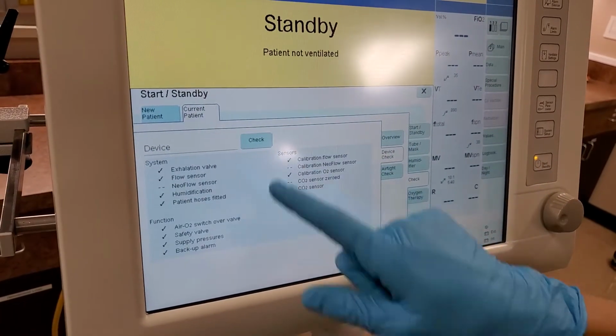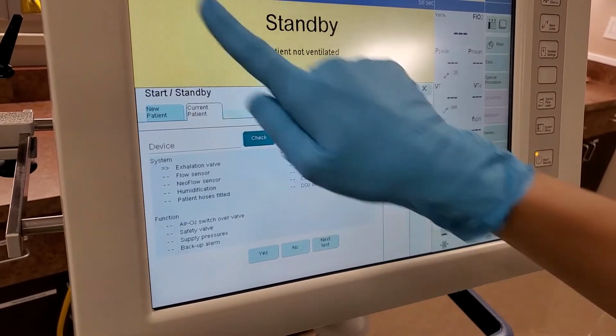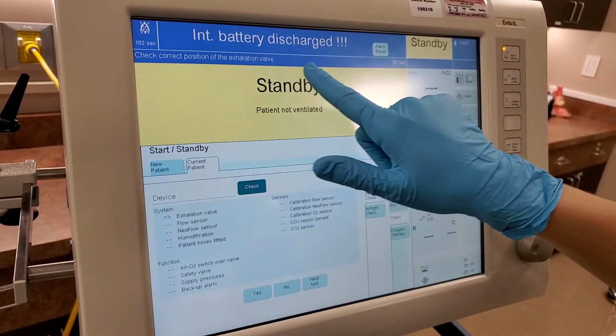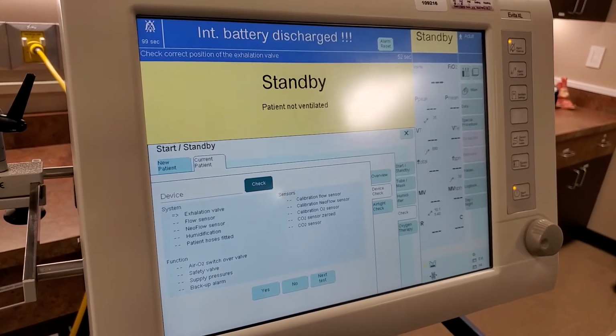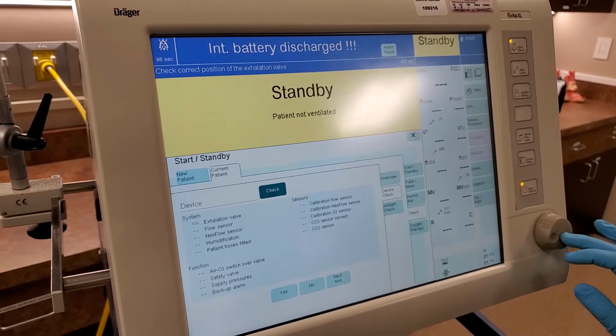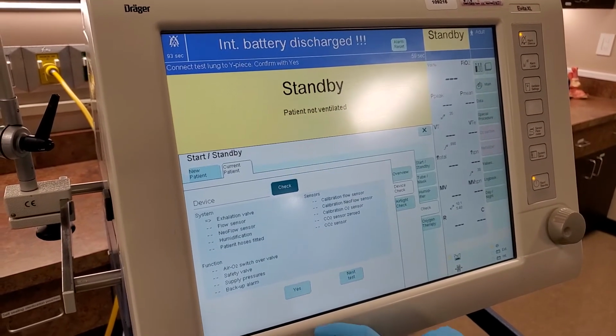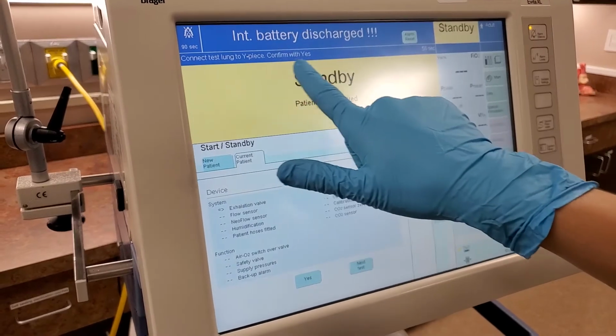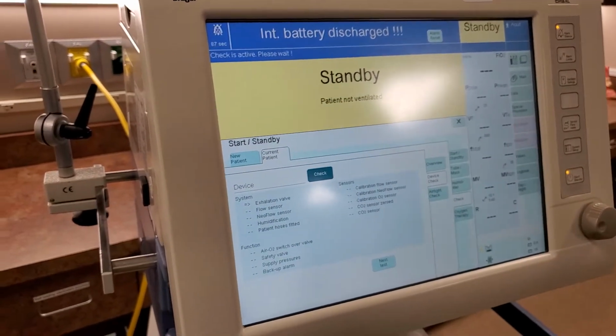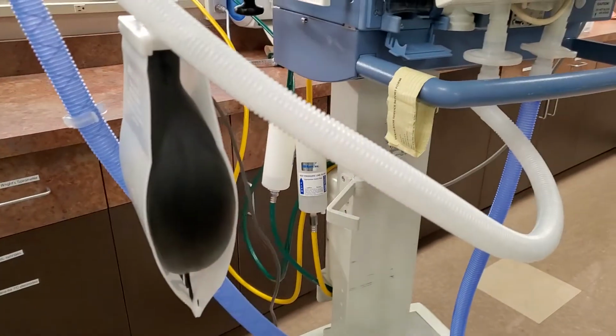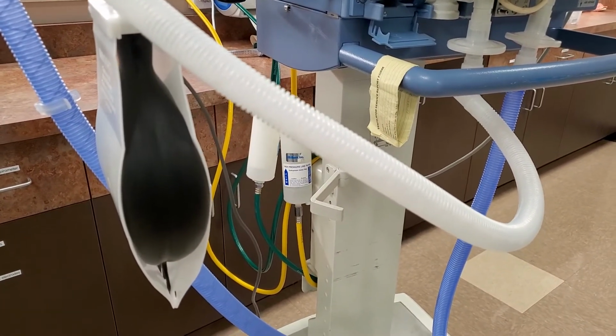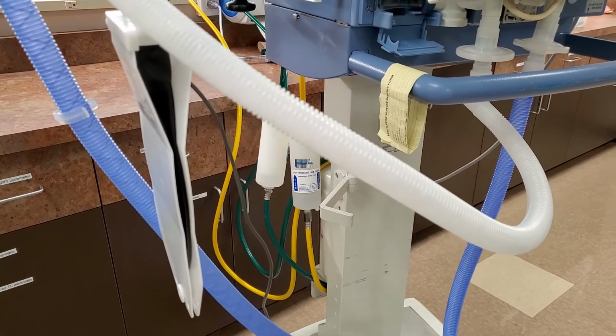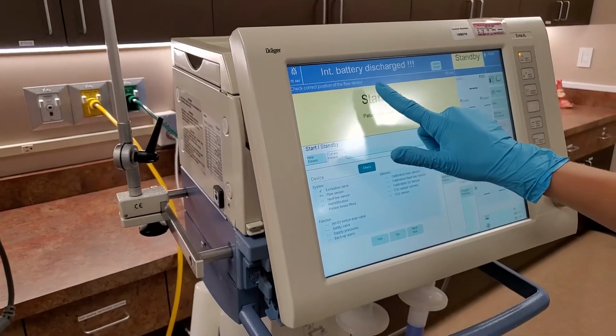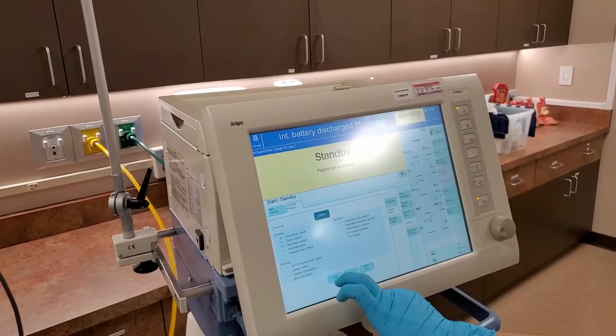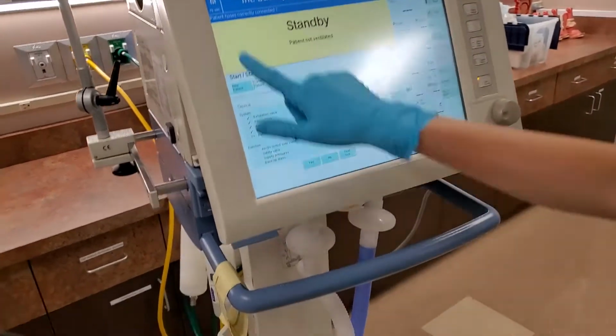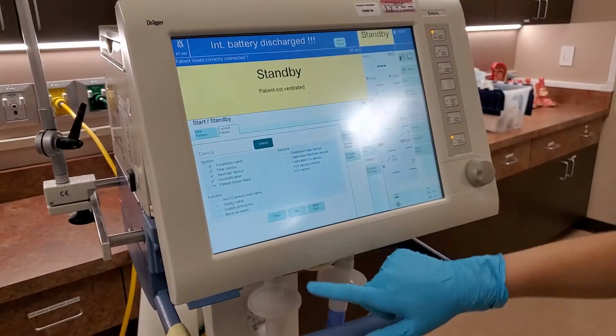To start the device check, you just hit check, and it's going to tell you what to do based on the directions right here. Right now it's telling you to check the correct position of the exhalation valve, and if it's good, then just hit yes. And it says connect the test lung to the Y-piece, confirm with yes. Now it's checking. Now it's telling you to check the correct position of the flow sensor. It says patient hoses correctly connected. Yes.